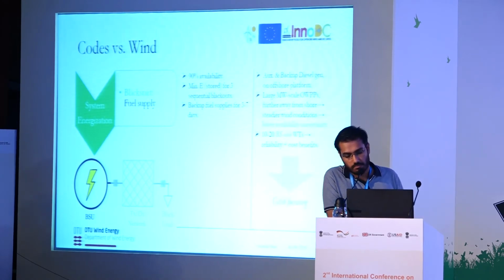Blackstart units are required to have 90% availability so that, in case of a blackout, the service can be provided. If stored energy is used, then a minimum volume for 3 sequential blackouts is required, and also a backup fuel for a minimum duration. For example, in the case of UK National Grid, 3 to 7 days is required from grid codes. In this case, we don't have control over wind, so when the wind is not blowing, there is no Blackstart service, right? However, going deeper and deeper into the offshore, with larger and larger wind plants, maybe not megawatt scale but gigawatt scale now, can assure steadier wind conditions and thus lesser availability uncertainty.